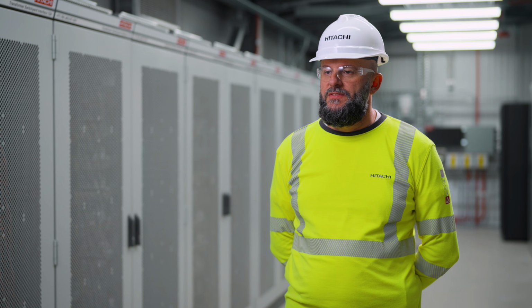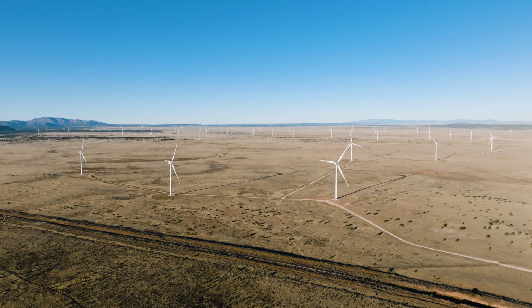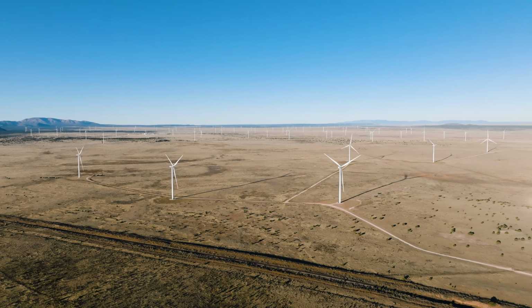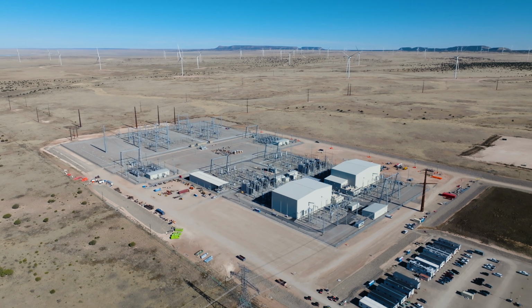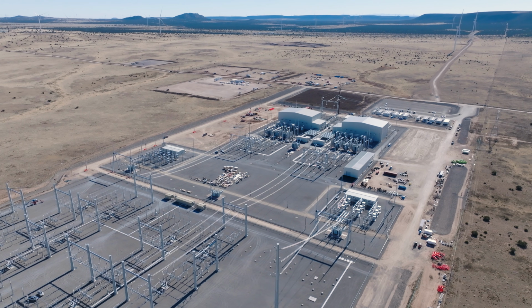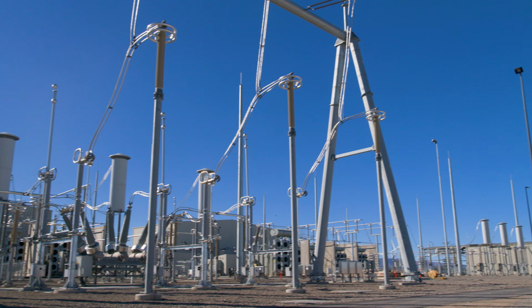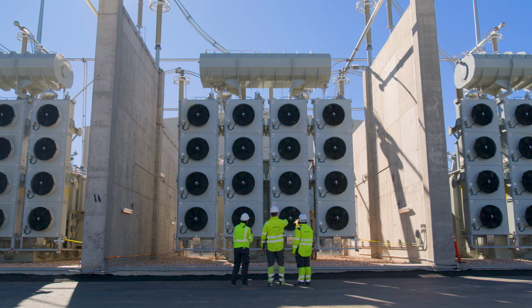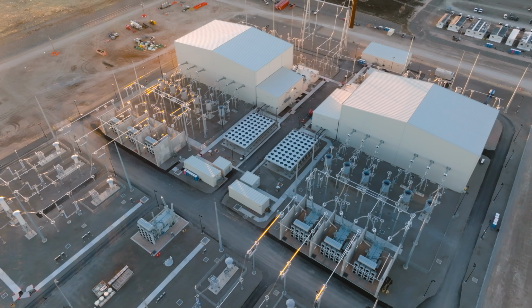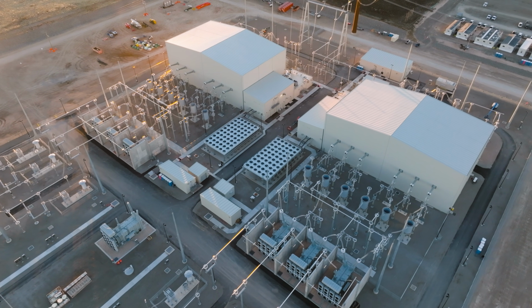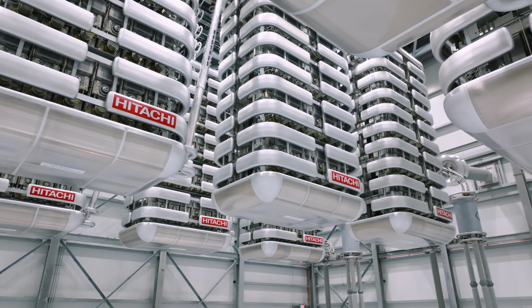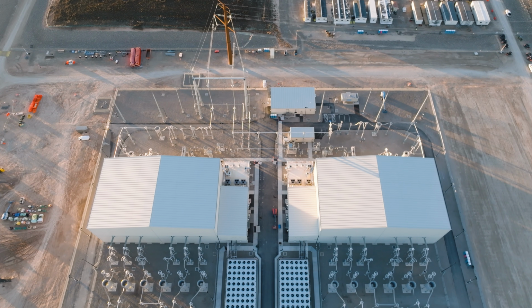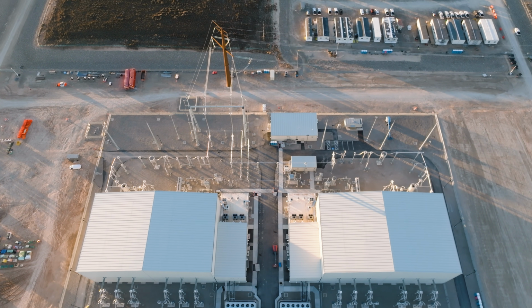SunZia project is made up of 916 wind turbines. The energy produced by the wind farms goes through underground and overhead collection line systems to the HVDC stations. This power enters the AC area, flows through the converter transformers and reactor area into the valve halls, where it gets converted from AC to DC and is sent via transmission line to the West Station in Arizona.